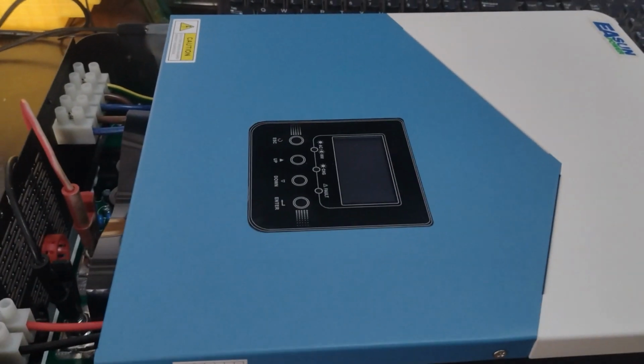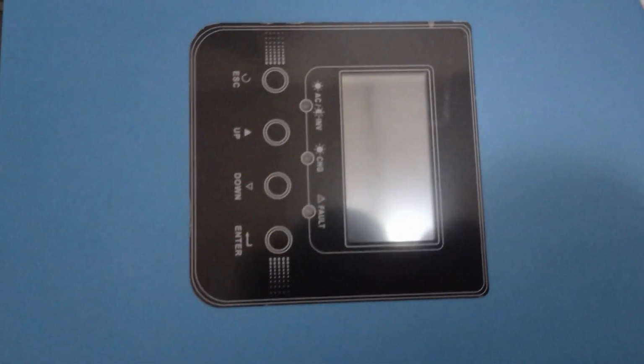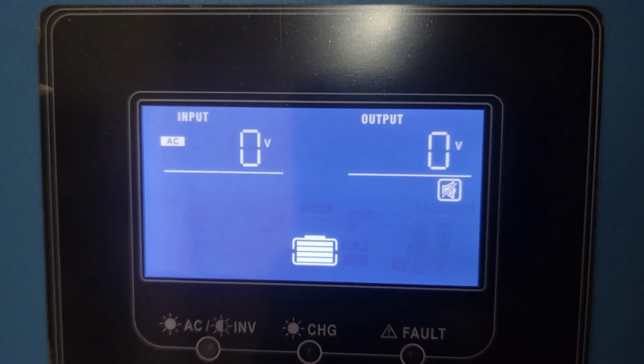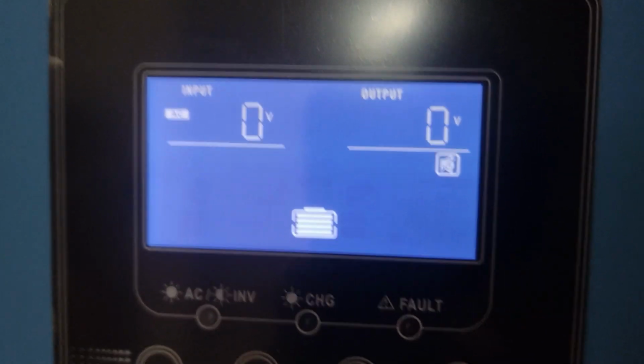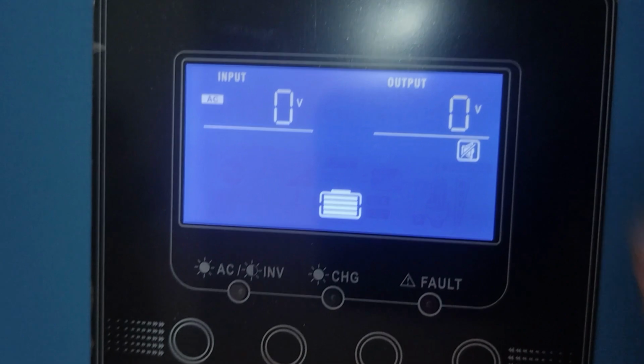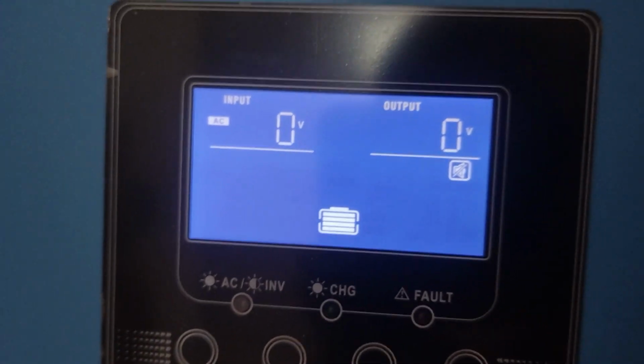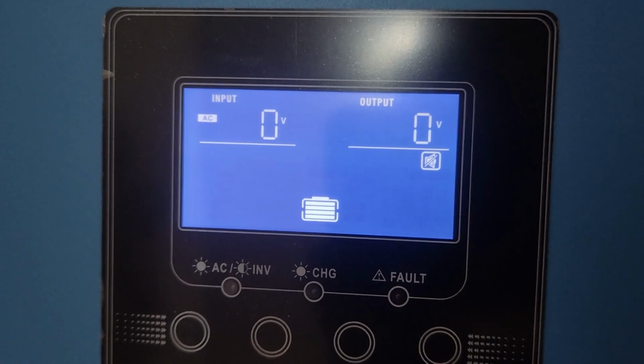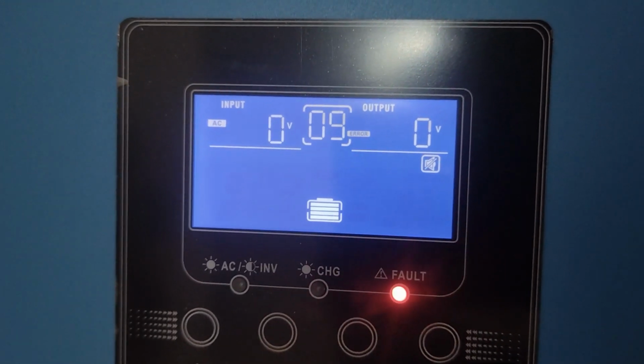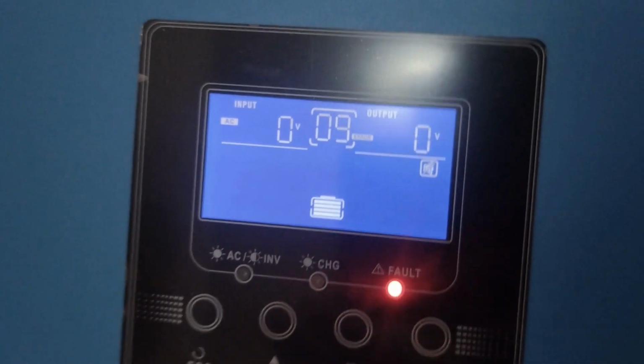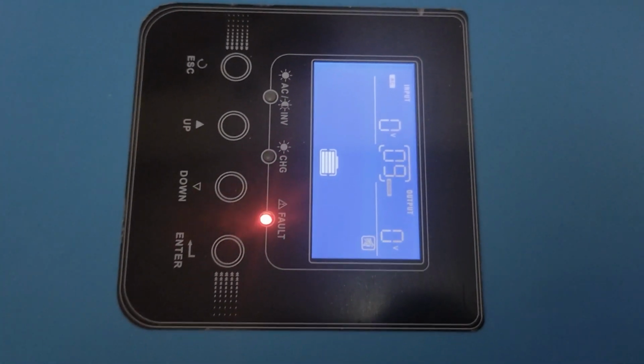It's a 6.7 kilowatt. No information on it, just that it doesn't work. So we'll power it up. This little guy. Alright, so there is life, that's good. Should be seeing 240 volts here on the output, but so far nothing. Not a good sign. And there we go, fault 09. Let's go check what fault 09 is.